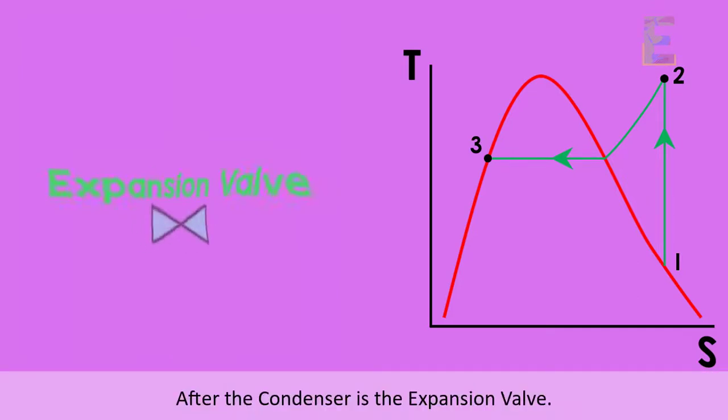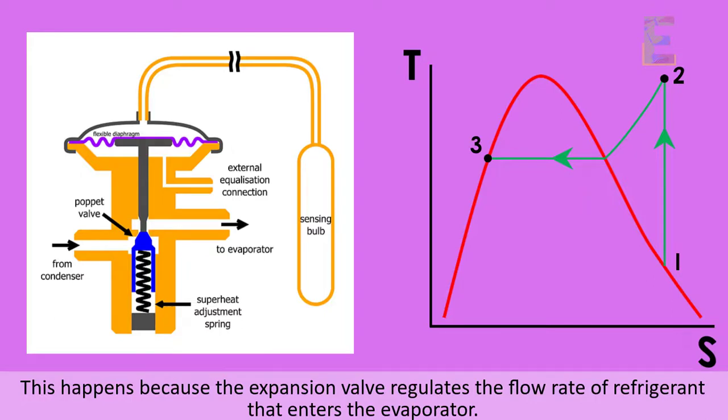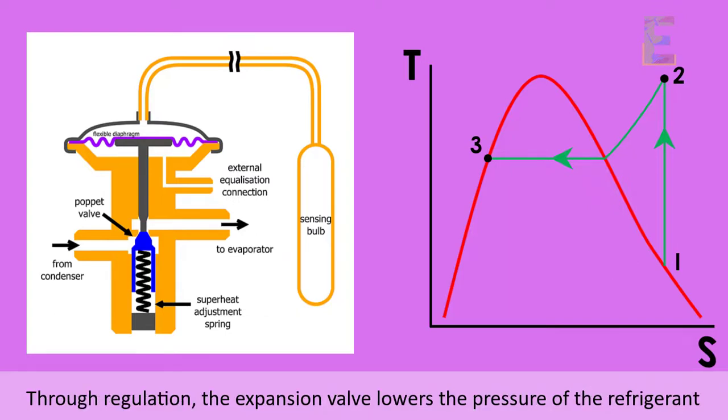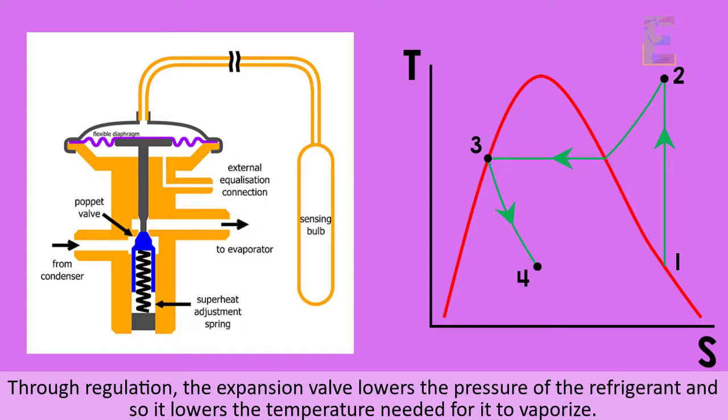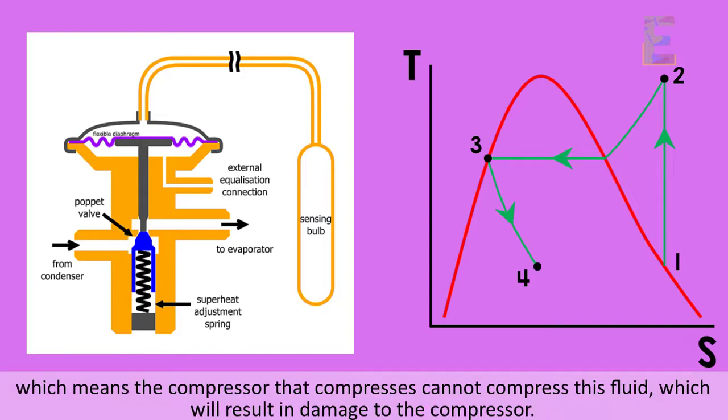After the condenser is the expansion valve. The refrigerant enters the expansion valve as a liquid and exits as a mixture of liquid and partly vapor. This happens because the expansion valve regulates the flow rate of refrigerant that enters the evaporator. Through regulation, the expansion valve lowers the pressure of the refrigerant and so it lowers the temperature needed for it to vaporize. The lower the pressure, the lower the boiling point. In addition, the expansion valve ensures that the refrigerant exiting the evaporator is a superheat and no liquid is present as liquids are incompressible, which means the compressor cannot compress this fluid, which will result in damage to the compressor.